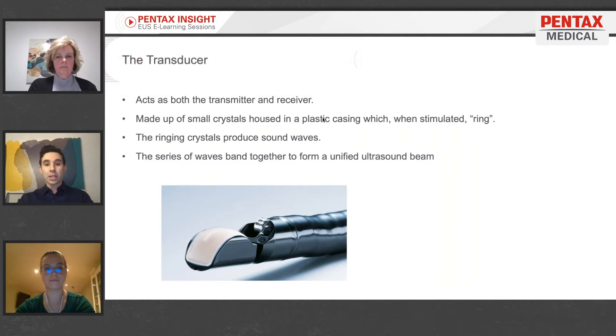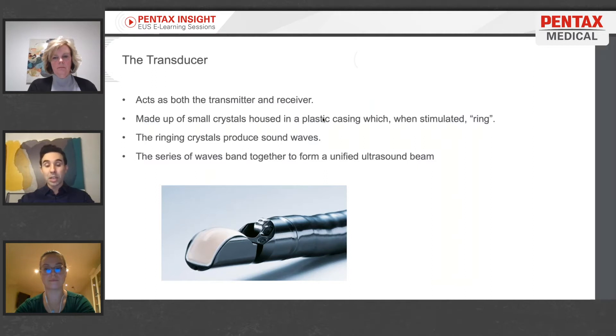What is in the transducer? The endoscopic ultrasound scopes house a small transducer made up of tiny crystals that, when stimulated, will ring. That ringing is what emits the endoscopic ultrasound wave. That wave transmits from the tip of the endoscope or probe into the adjacent tissue being targeted by the endoscopist. Those waves ultimately band together to form one unified beam that is received back into the probe, and an image will be generated.